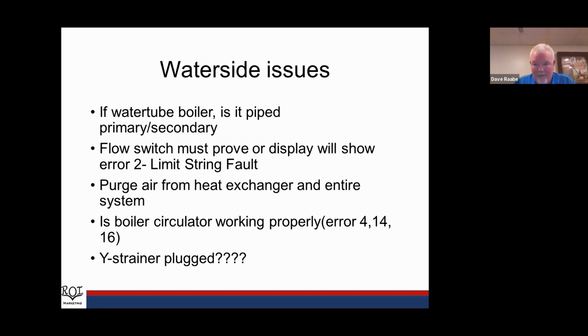Again, the flow switch must prove water flow, or the display is going to show error 2, limit string fault. And we need to then research that and determine why we are not getting flow through that boiler. There may be a couple reasons for that: air in the system or air in the heat exchanger. So you need to purge air from the heat exchanger and out of the entire heating system. We provide an air purge fitting on our heat exchanger that has probably a 10-inch flexible black tube connected to it. Makes it real easy to get the air out of the heat exchanger. And US Boiler has some short videos available on their website, one of which is strictly about purging air from that heat exchanger.